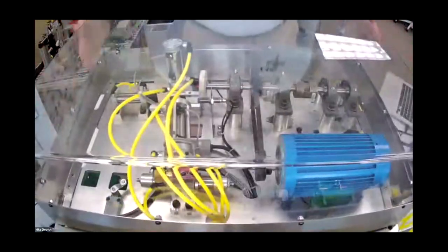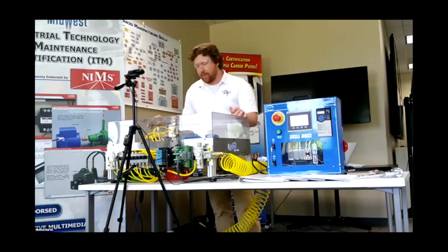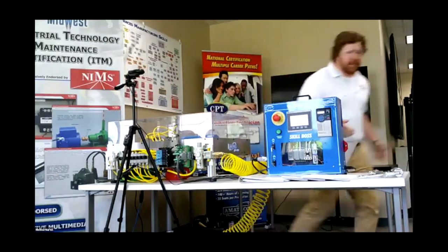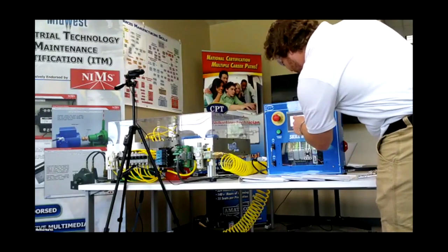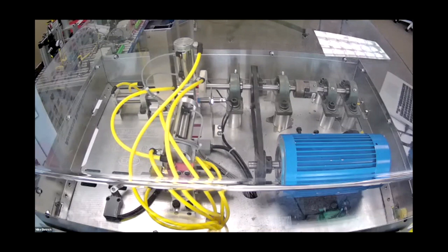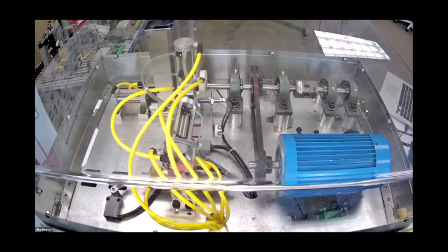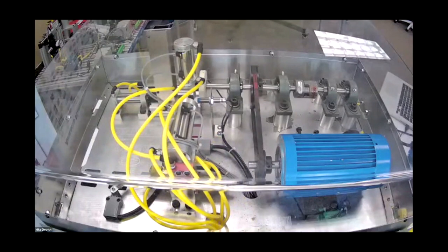All right, let's see how you did. So what I'm going to do is I'm going to put the locking mechanism on right now, and I'm going to open our air back up, and we're going to give it a test run. The first part that we're going to feed through is just going to be an acrylic part, and that's going to be our control. We'll be able to see where the program and where the mechatronic system actually sorts the acrylic piece, and then we'll run through a metal part to see if our adjustments work well. Again, working with proper lockout tagout procedures, giving control power. All right, here we go, Evan. This is our first plastic piece. So it looks like it passed the quality check, and when it moves forward, it's going to sort it to the far bin. So let's see if we made a good adjustment. Here comes our next aluminum piece.